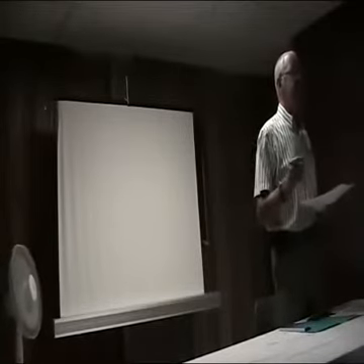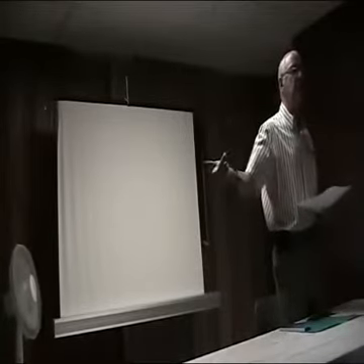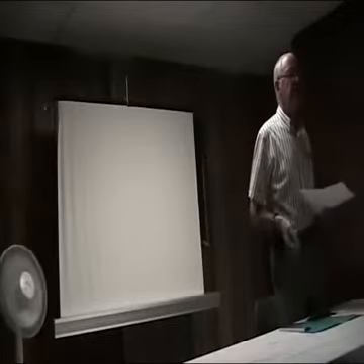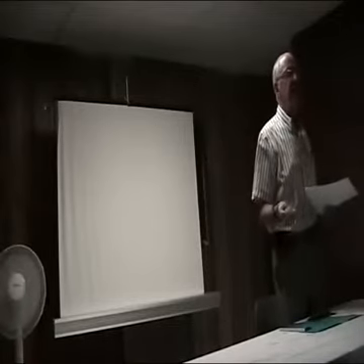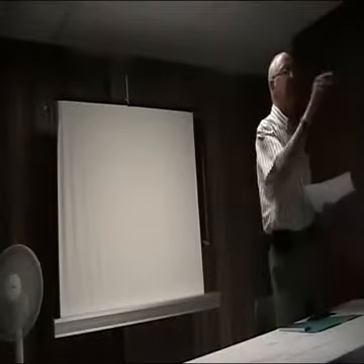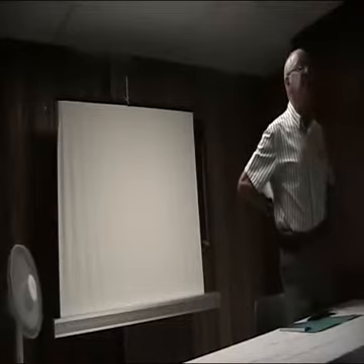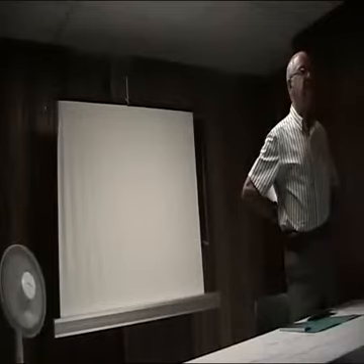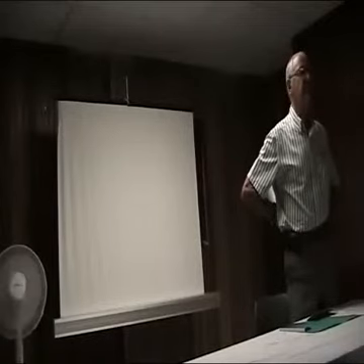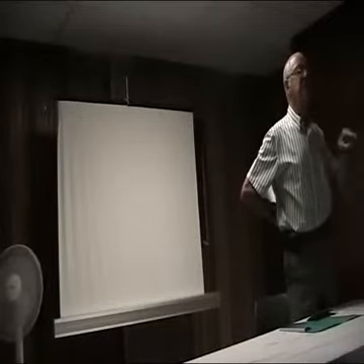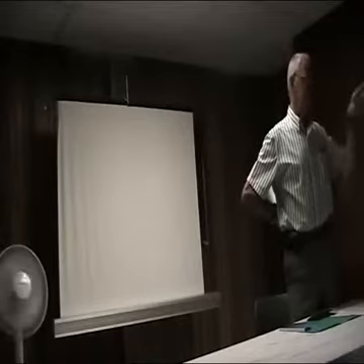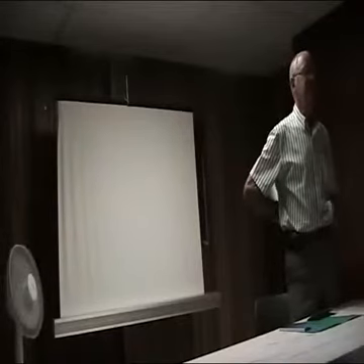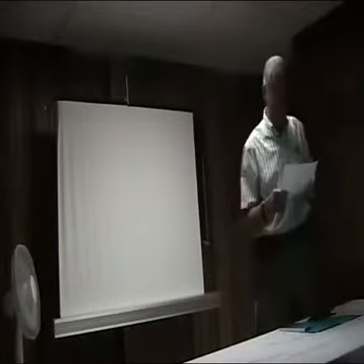Confirm the area classification. That comes in with your solenoid and your positioner. If you need ATEX and IA certification, you have to certify it on there. Otherwise, later on when you say, I want IA certification and ATEX, he says $800 a piece. Go and fetch the $800 a piece. It's $1,600. Go and get it from the boss. If you didn't specify it and you didn't quote for it, you're going to pay for it. They do that. Ask me. They do it to me regularly. Sometimes they're very good to me.